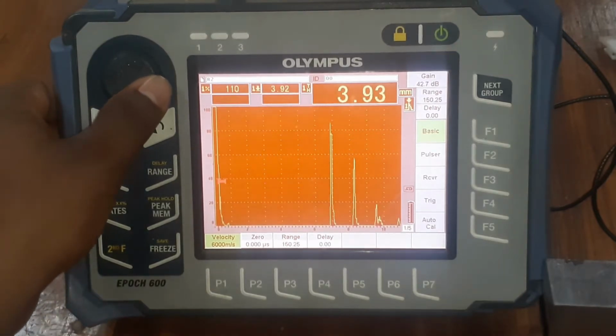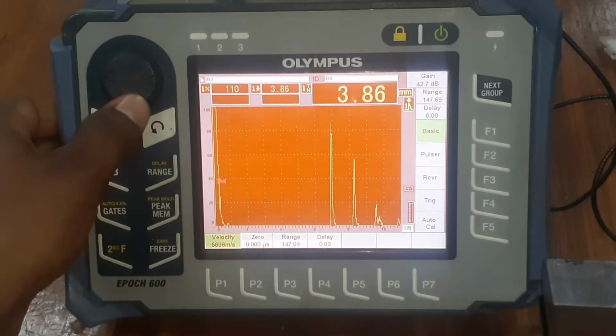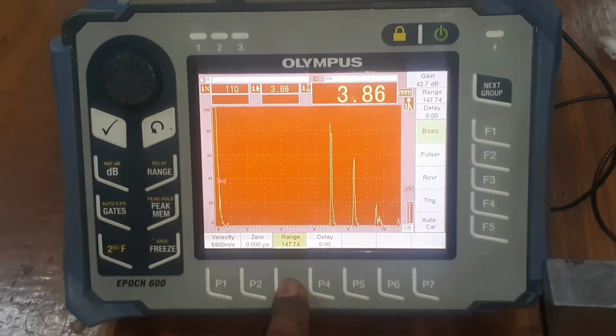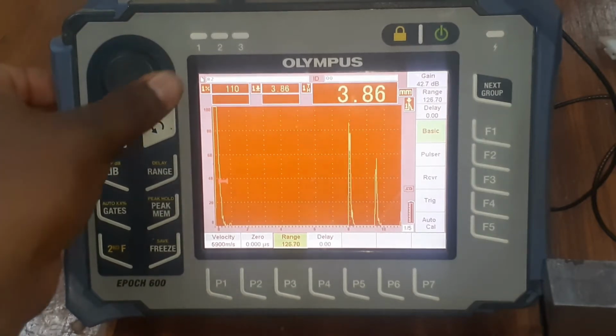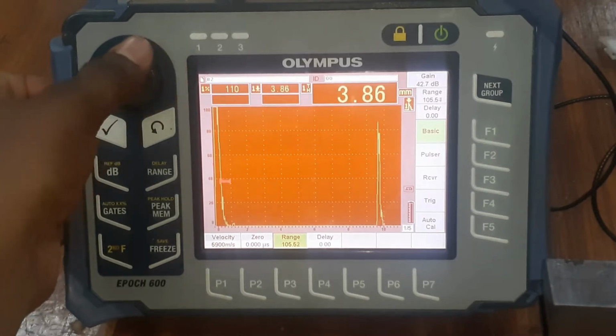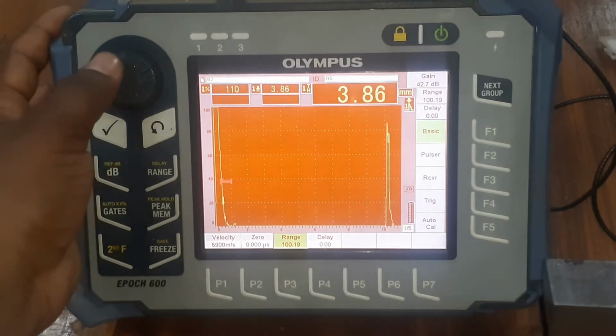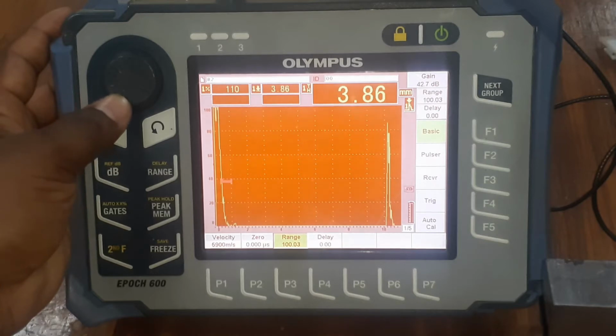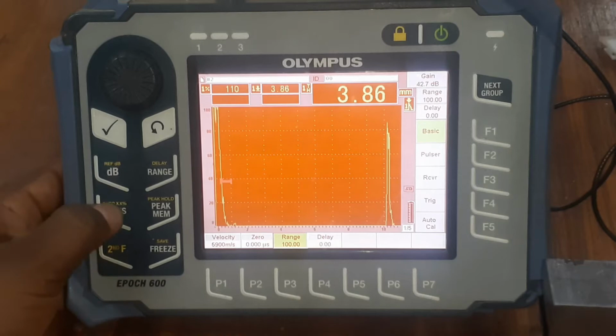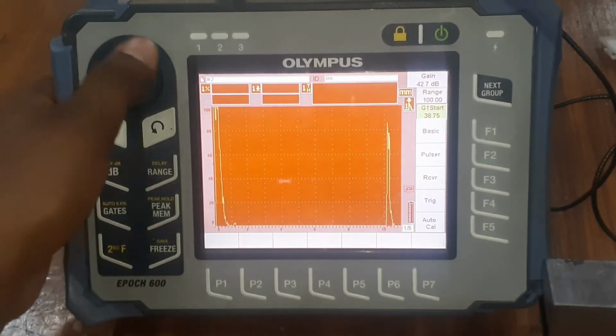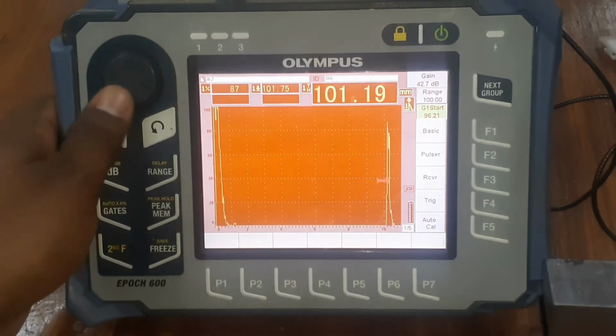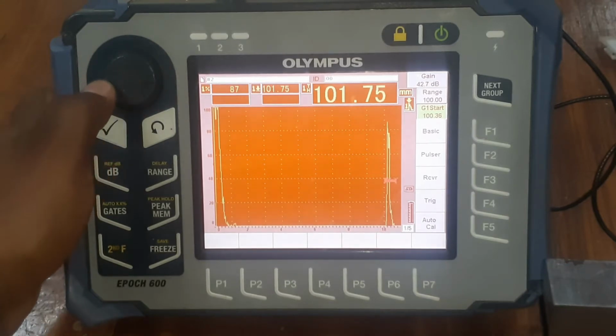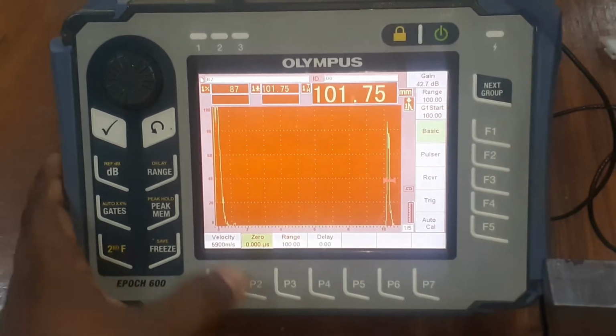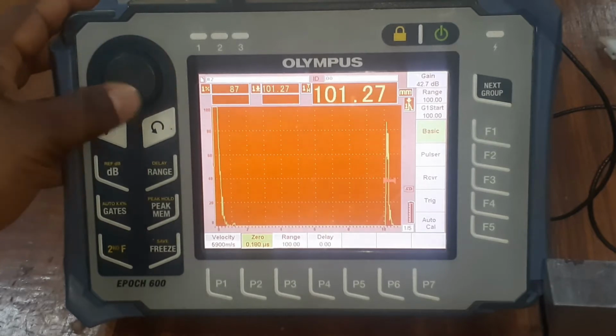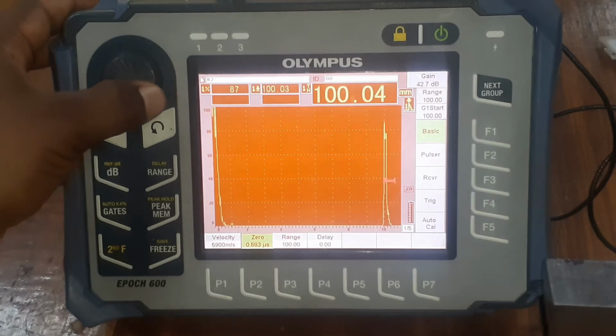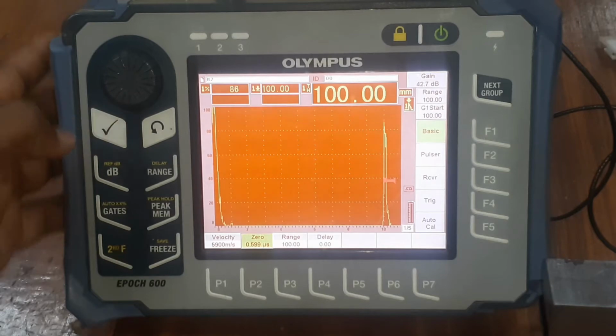First, you should change the velocity according to the normal probe. It should be 5900 meters per second, and then range set to 100 because of our calibration block. Maximum height is 100 millimeter. Then gate set onto the peak like this. We should set the actual value of 100 millimeter using the zero parameter value. Then the normal probe is ready for testing.